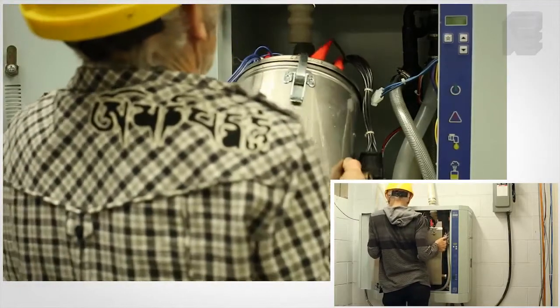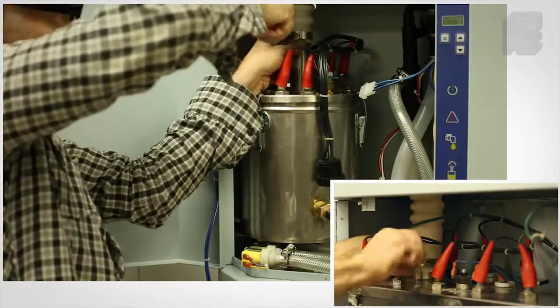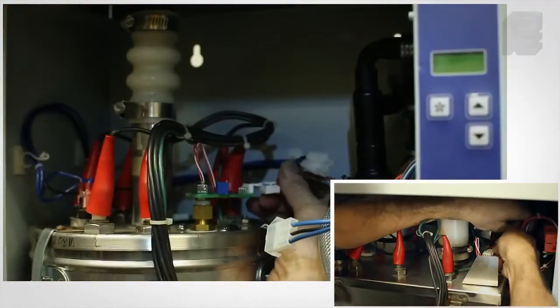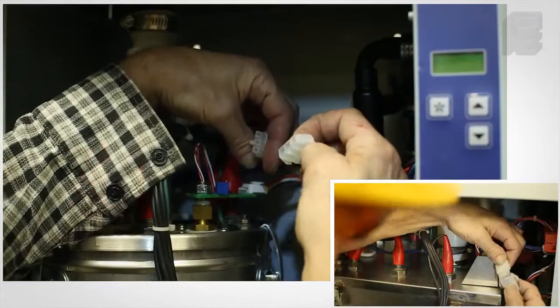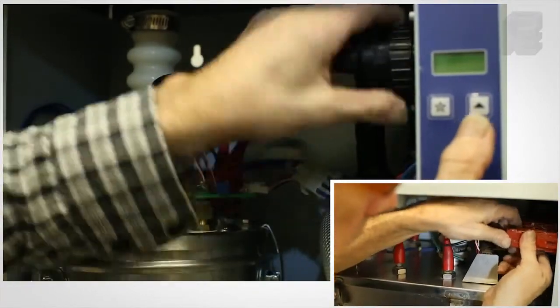Mount the boiling chamber back into the unit and attach and tighten the fill drain connector. Reconnect the steam hose and the three electrical connectors: level sensor, thermodisc, and heating elements. Make sure all are in place.